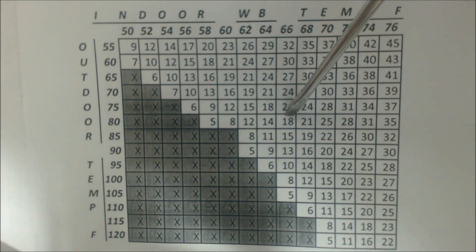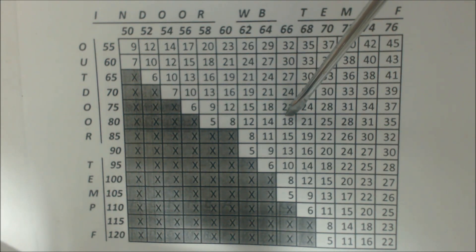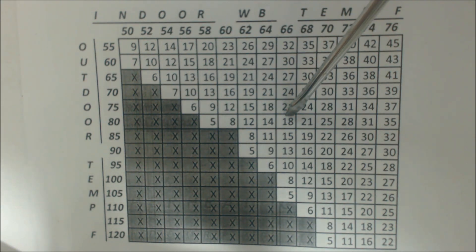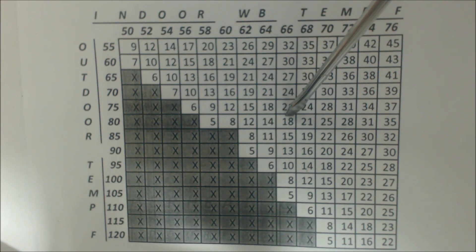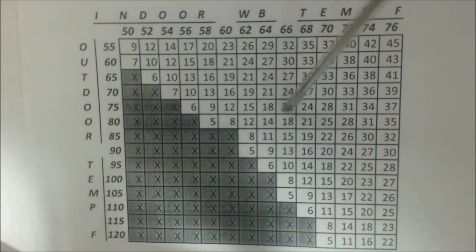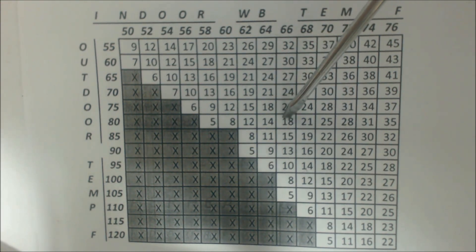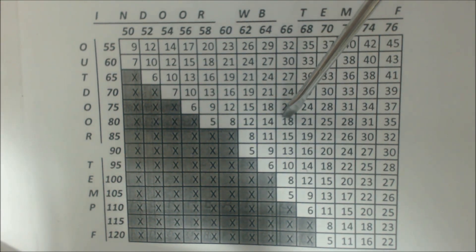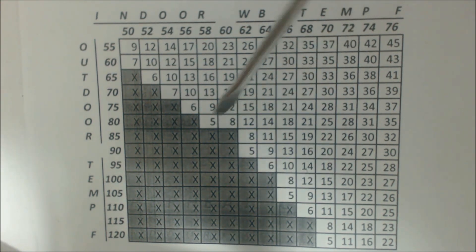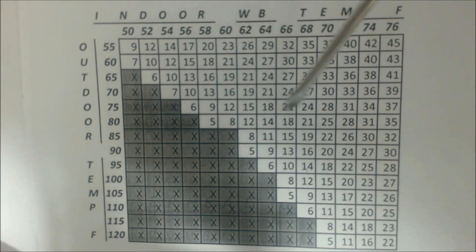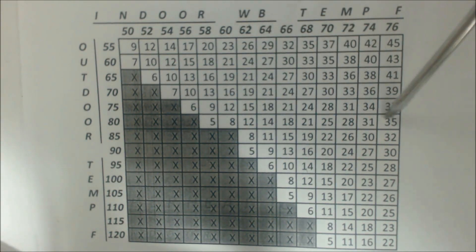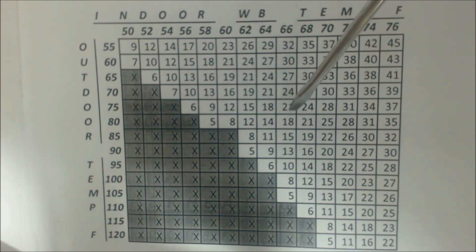That means that our suction line is 18 degrees higher than what our pressure on our blue gauge converted to saturated temp is. So our temperature increase in vapor form, our actual temperature on our suction line minus the saturated temperature on the blue gauge should be 18 degrees of superheat. If it's lower than that, that means there's too much refrigerant. If it's higher than that with superheat, then that means you need to add refrigerant to it.